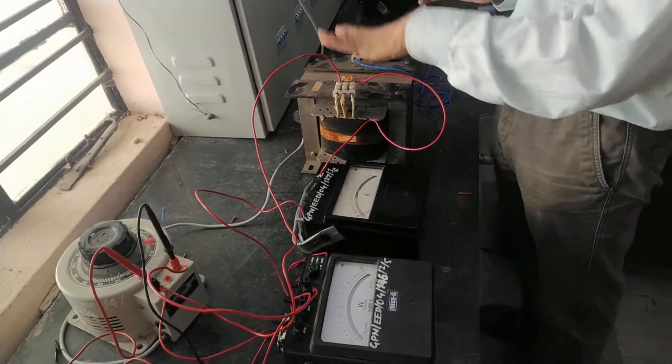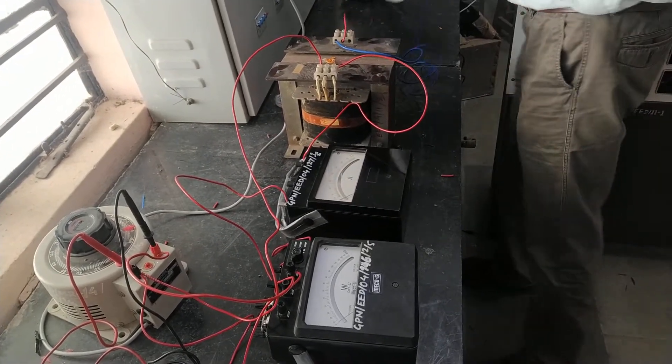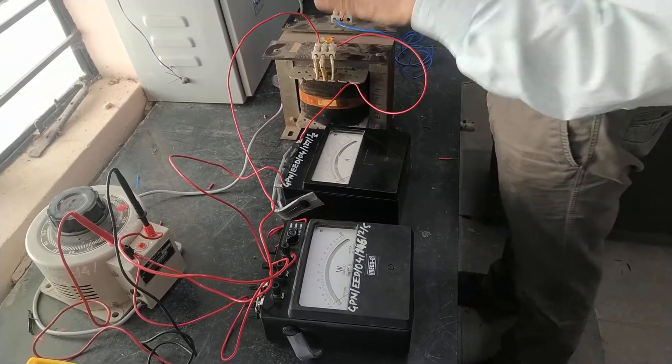To variac we are going to connect rated voltage across the primary of the transformer, secondary we are going to keep open, secondary terminals are being kept open, and we have to apply rated voltage across the primary.